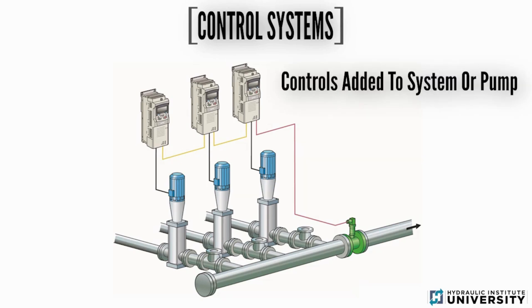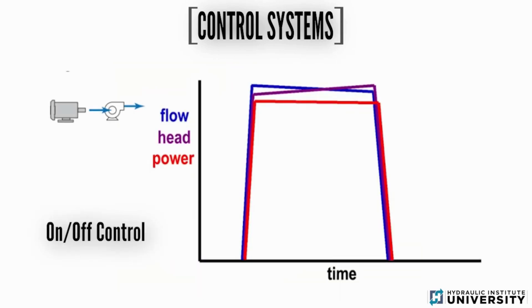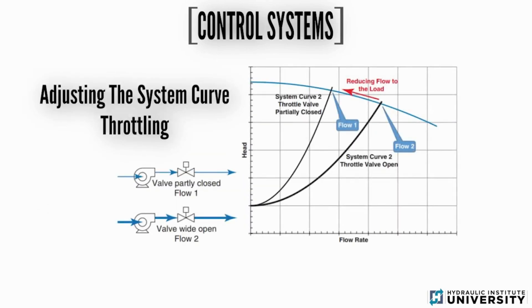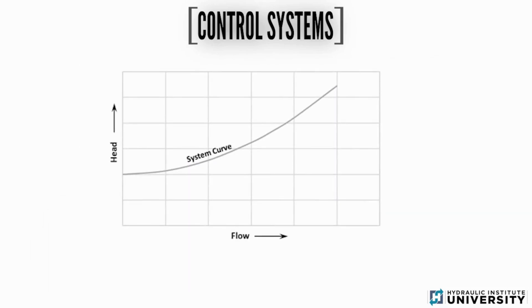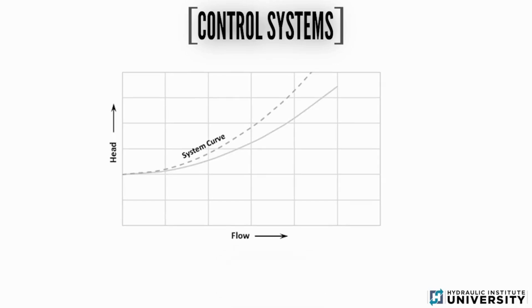Control systems are added to the system or pump. This can be done in three ways: by turning the pump on and off based on demand, by adjusting the system curve, or by adjusting the pump curve. The system curve can be adjusted by throttling a valve, which restricts fluid flow, creating additional friction losses or pressure drop across valves.